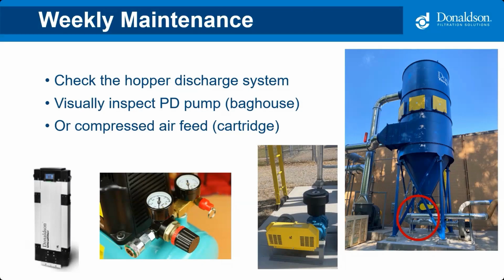A good trained maintenance person can understand when something's making noise that it shouldn't be making. You're just confirming that it doesn't have any air leaks. We don't want to be introducing any air outside of the air that we're flowing through it with the fan. And you're just audibly checking for any sounds or noises that are abnormal that could be indicative of a bigger issue with bearings or something like that. The last two items are basically the same thing but different for different types of collectors. On a bag house, most bag houses will use a positive displacement pump, or we just call it a PD pump. There's a picture of it down there in the center right with the yellow fan shroud around it.